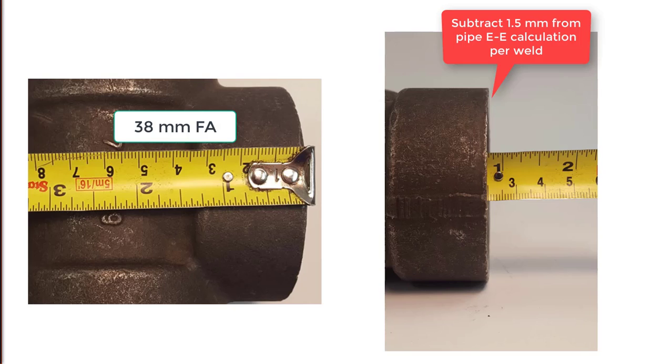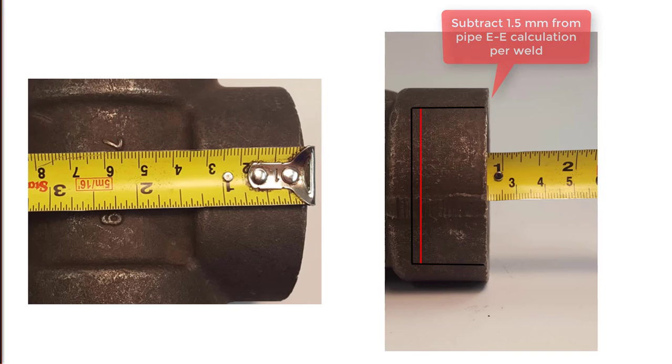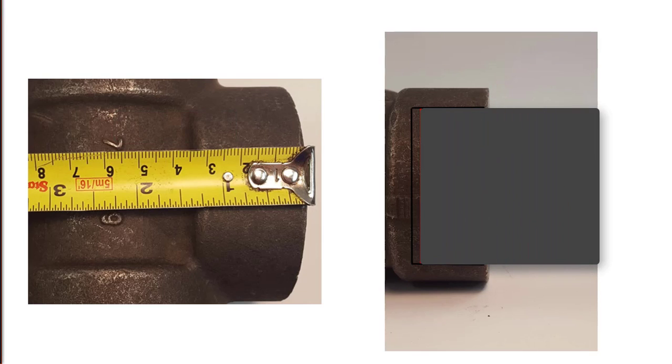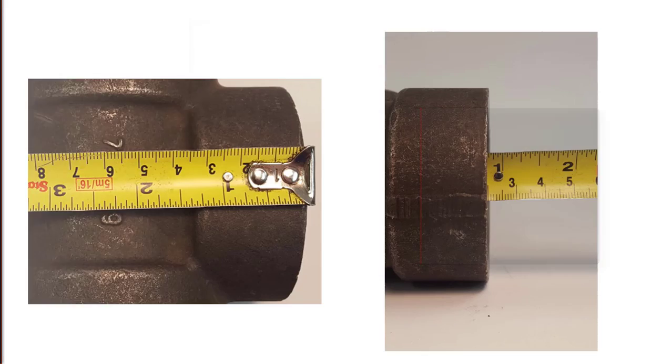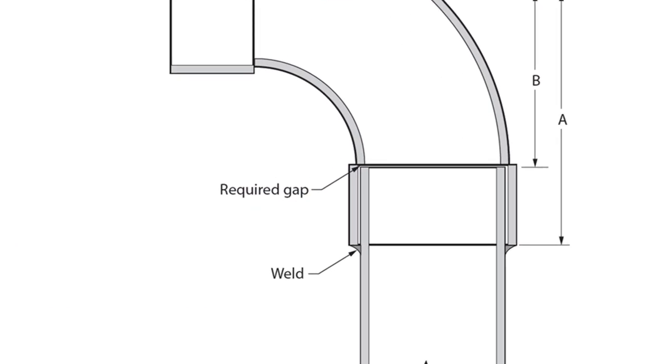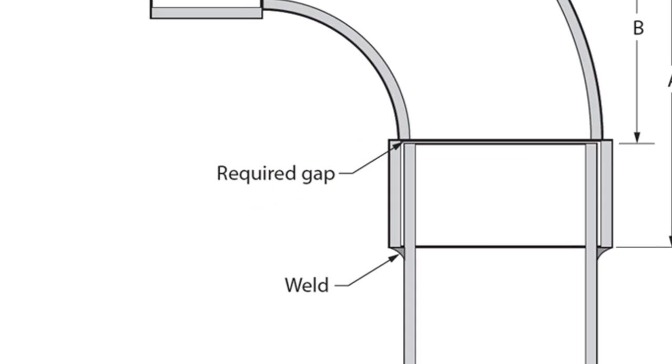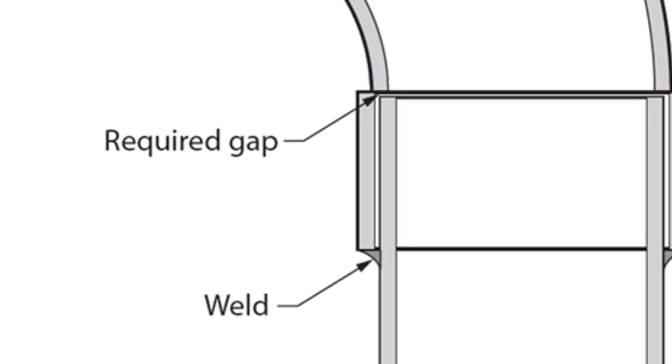Now that was all pretty much review of the threaded pipe fitting allowance process other than the expansion gap. I'd like to talk now about setting that gap. The gap is too small to try and slide the fitting out of the socket to set it. You would have difficulty being consistent without marking the pipe, which of course takes time. The other thing that you have to account for when tack welding fittings is the cooling contraction or pulling of the weld that takes place.